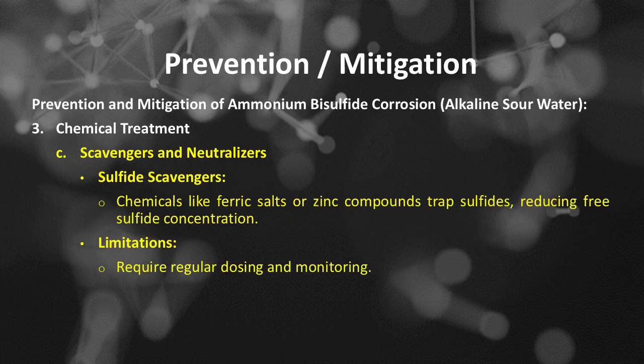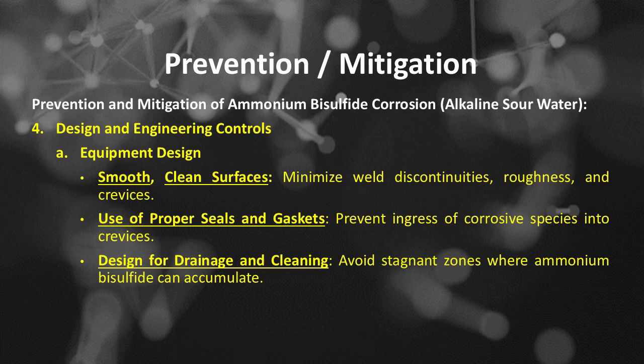Chemical treatment, number C, is scavengers and neutralizers, including sulfide scavengers, chemicals like ferric salts or zinc compounds that trap sulfides, reducing free sulfide concentration. The limitation of scavengers and neutralizers is that they require regular dosing and monitoring.